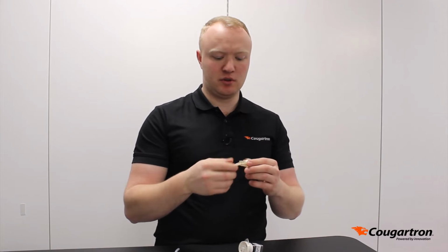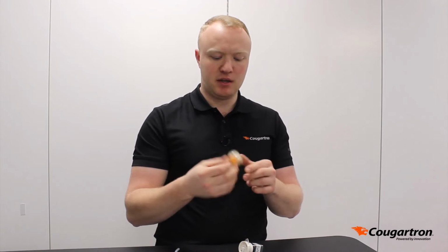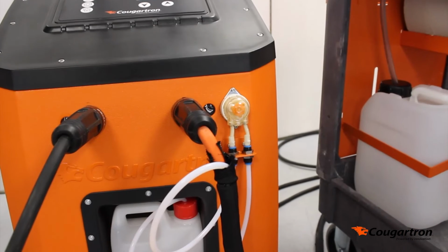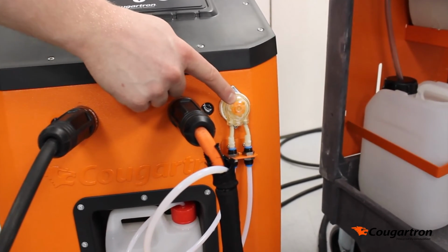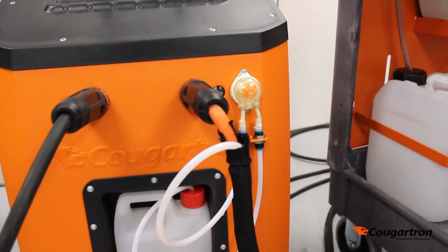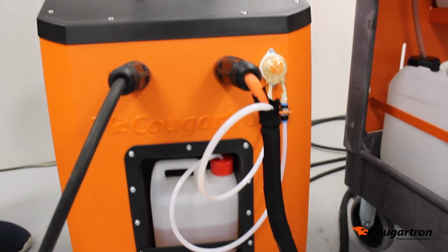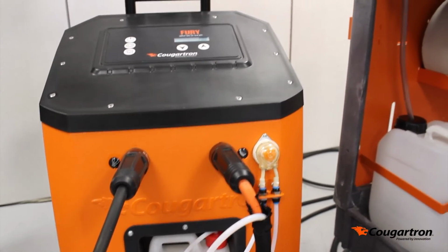This part here can be easily replaced. This is a flexible tube in the peristaltic pump, and this is a spare part, so if you need to replace the pump head, you just unclip the old one, clip the new one in, and you're good to go. And besides that, the acid is out of the machine. You can see on the machine that we've got a 1 litre holder, and the tubes are all out of the machine, so there's no damage to the electronics because the acid is out of the machine and the electronics are inside the machine.